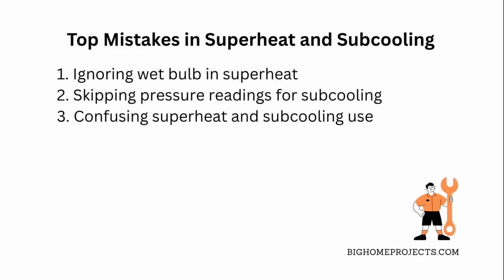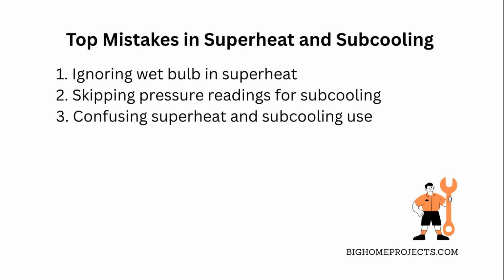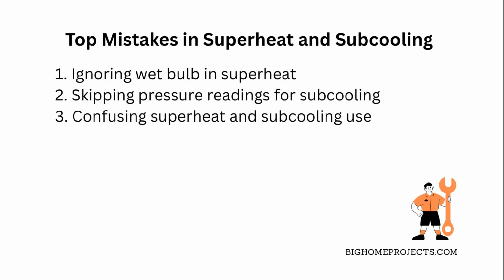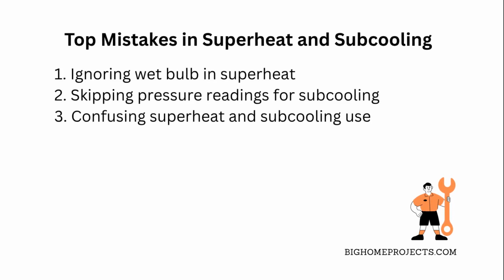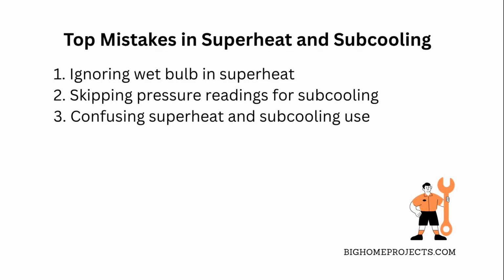Third, folks often confuse when to use superheat versus subcooling values, messing up diagnostics. Remember, superheat is on the evaporator side, linked to indoor conditions. Subcooling is on the condenser side, focusing on pressure and temperature only. Stick to this rule for clear results.